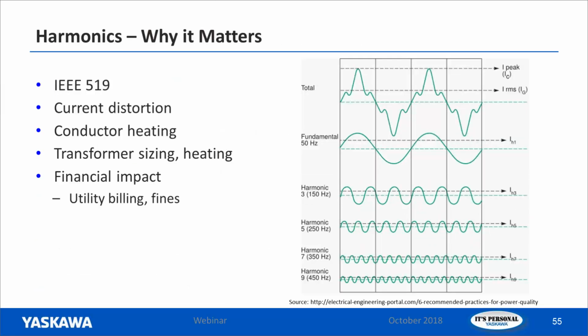I mentioned the integers of the harmonics. So here we've got the 9th harmonic, 7th, 5th, 3rd. Each of these gets added onto the fundamental frequency that you've got. In this case, it's a 50 hertz example. That was the closest I could find. But when they all get added on to that sine wave, this is what you get. This is what it ends up looking like.